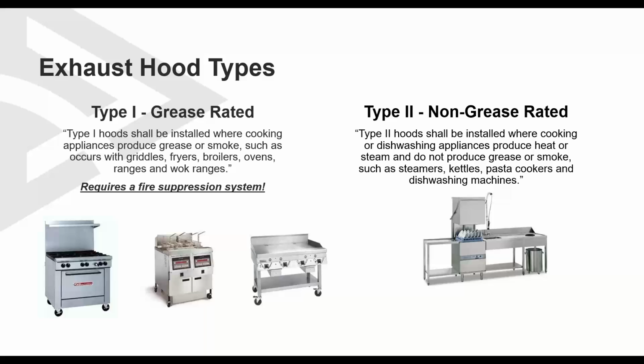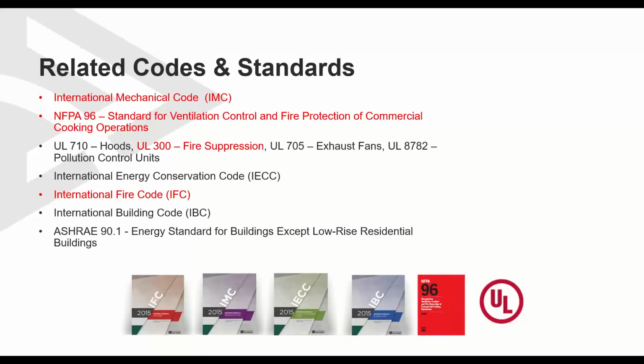Moving on to the exhaust hood types, we have type 1 and type 2 hoods. Type 1 hoods are grease rated versus type 2 are non-grease rated. We're going to focus more around the type 1 hoods today because these hoods require a fire suppression system. Most type 1 hoods are found above appliances such as griddles, fryers, broilers, ovens, ranges, and wok ranges. We follow a variety of codes and standards. The ones that I have highlighted in red directly relate to specific fire codes that we follow.